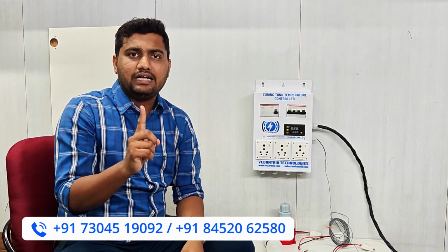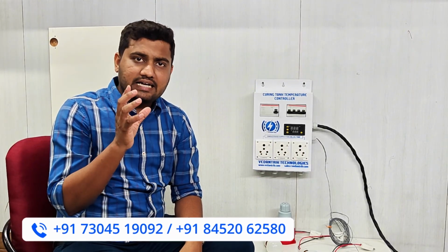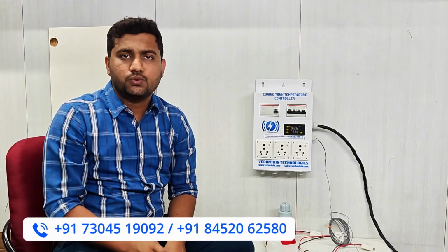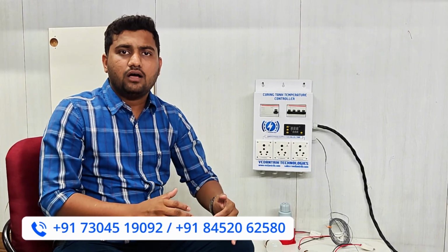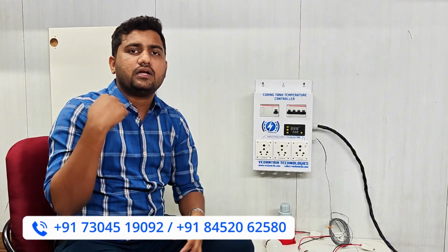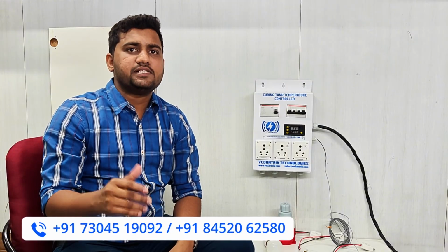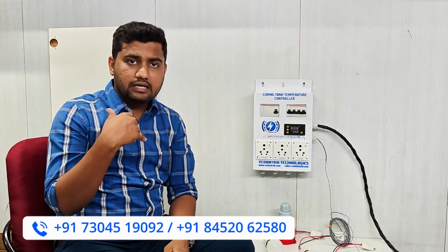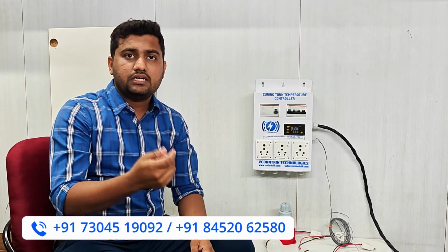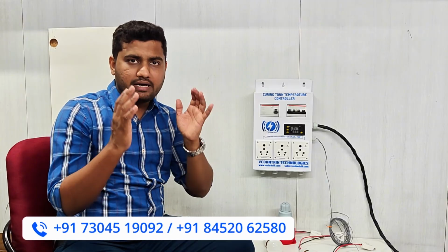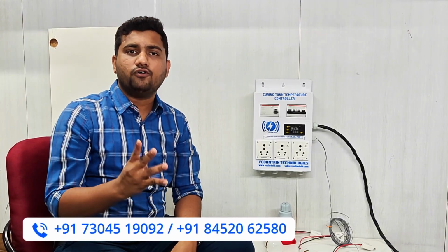We will give only one heater of 4 kilowatt capacity, and that is more than enough to maintain the 27 plus minus 2 degrees Celsius of temperature in the tank of capacity 3000 liters. So suppose if you have 6000 liters capacity of the tank, you can go for 2 heaters of 4 kilowatt each, that means 8 kilowatt. Like that you can increase the quantity of the heaters, but understand that the maximum number of heaters you can connect with this controller is 4. Because if you increase more heaters, the current will increase. So that's why, by taking care of the controller, we can connect only 4 heaters of 4 kilowatt each with this controller.